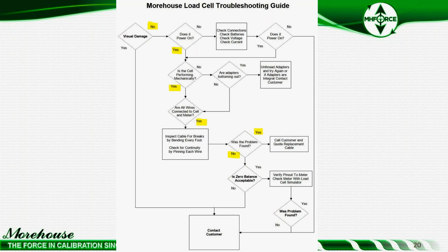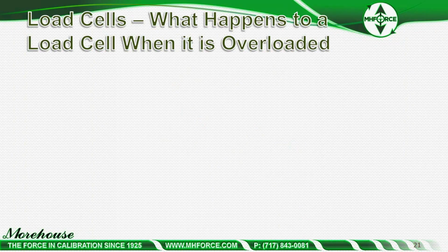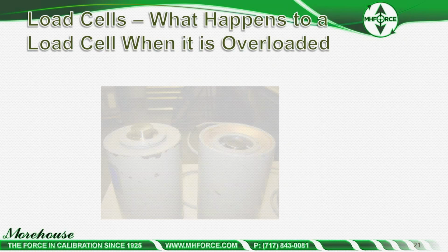If you don't find the problem, is the zero balance acceptable? And then you look if it's overloaded or not. So there's a nice flow chart. Again, if anybody wants a PDF copy of this, they can grab it and they can take the flow chart. So what happens? So we talked about the cell, the last step 7, we're saying is the cell overloaded. What happens to a load cell when it is overloaded?